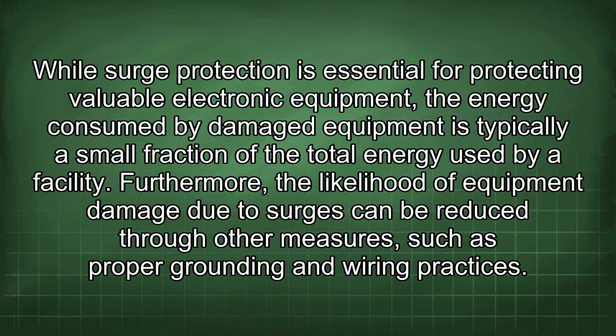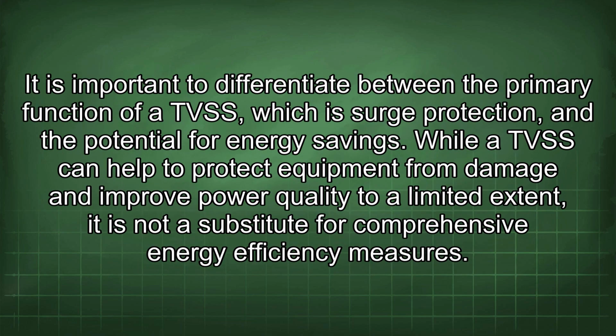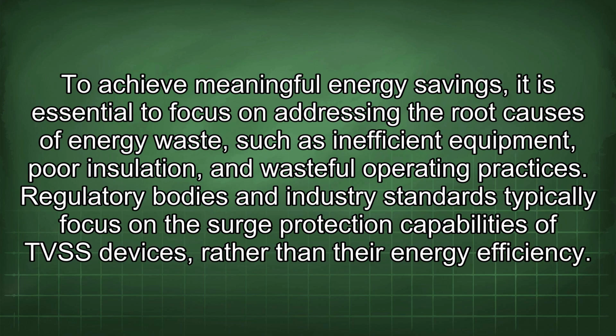Furthermore, the likelihood of equipment damage due to surges can be reduced through other measures such as proper grounding and wiring practices. It is important to differentiate between the primary function of a TVSS, which is surge protection, and the potential for energy savings. While a TVSS can help to protect equipment from damage and improve power quality to a limited extent, it is not a substitute for comprehensive energy efficiency measures. To achieve meaningful energy savings, it is essential to focus on addressing the root causes of energy waste, such as inefficient equipment, poor insulation, and wasteful operating practices.